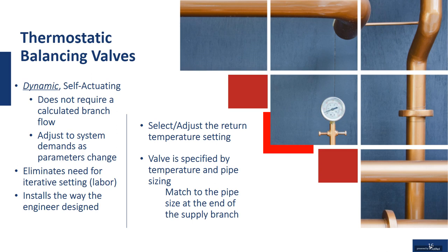The other thing you have to worry about, in addition to selecting the right temperature, is specifying the size of the valve. Basically, you'll size the valve according to the size of the piping in the branch or riser. So if it's a 1/2-inch branch or riser, you use a 1/2-inch balancing valve. 3/4 inch, you'd use a 3/4 inch. So you just match the valve to the pipe size.